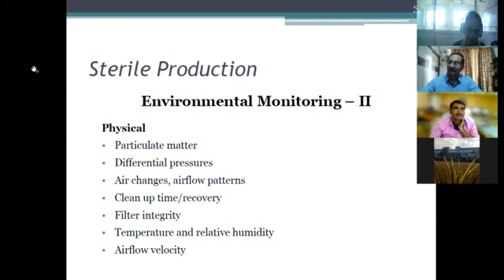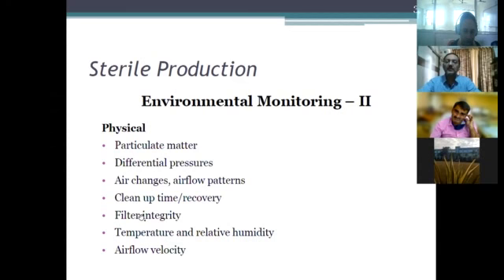In our laminar flow benches, which we are using where the filling operation is taking place, that's a grade A area. You cannot place a laminar flow bench in a common area. Otherwise, you will not get the quality of air, right? So that is how the cascade of cleanliness has to be maintained. So that is the physical monitoring of the environment. These are the parameters which are to be monitored when we are using aseptic areas. This has to be done regularly at time periods.